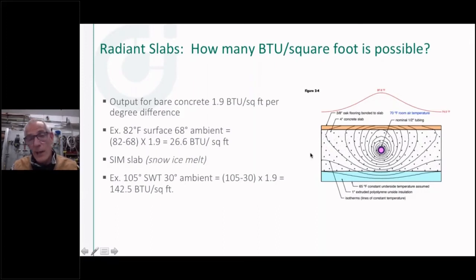Now, if I was in a shop building where people are in work boots or something all the time, I could raise that surface temperature a little bit higher and get a little more output out of that slab. Again, in a residential application where people might be walking around barefoot, they certainly don't want to have to put shoes on because the floor temperature is too hot. So that's really the driving factor on what heat output you can get per square foot of a slab. Obviously, as you start putting floor coverings on that, you're putting R value on there, and you're limiting that output.